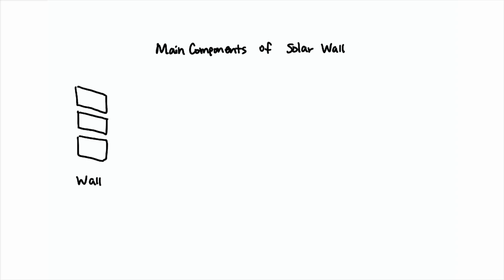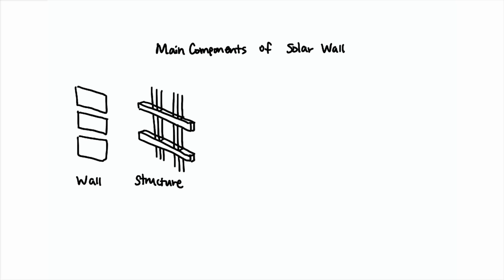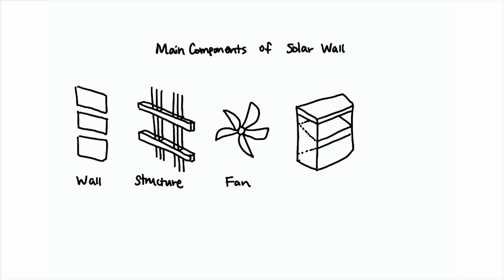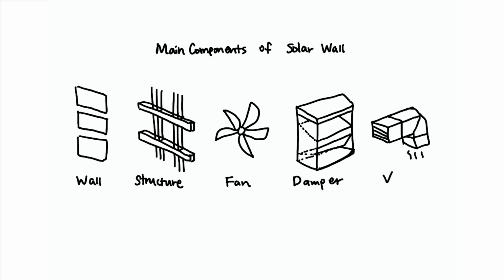The solar wall and its related products, which we'll refer to as just solar wall from now on, introduce a simple concept in controlling the heat in the building. It uses five main components: a solar collector to absorb the sun's energy, a structure that allows for an air gap between the wall and the solar collector, a fan to draw air in, a unit with dampers that controls the flow of air, and finally ductwork that allows the air to be delivered.